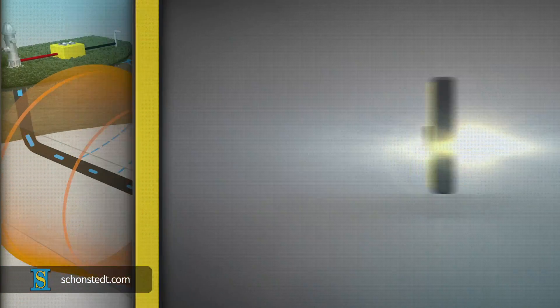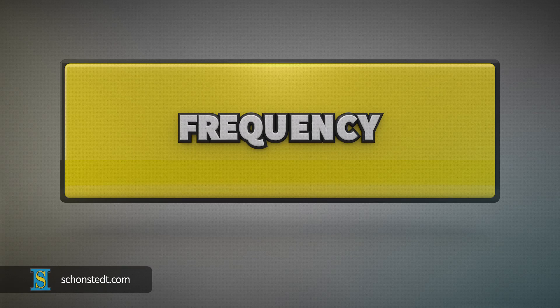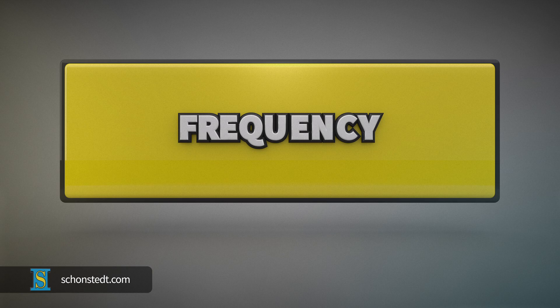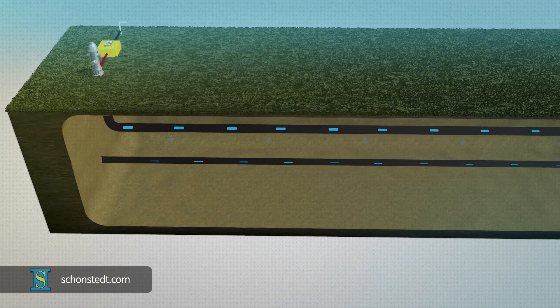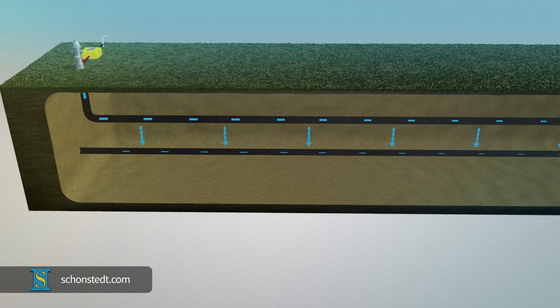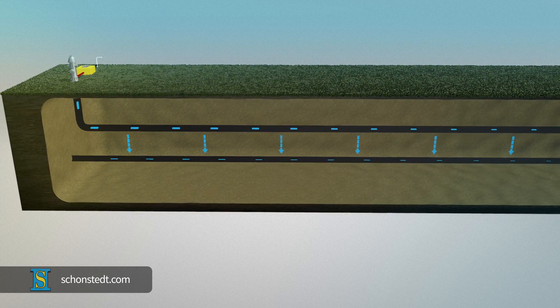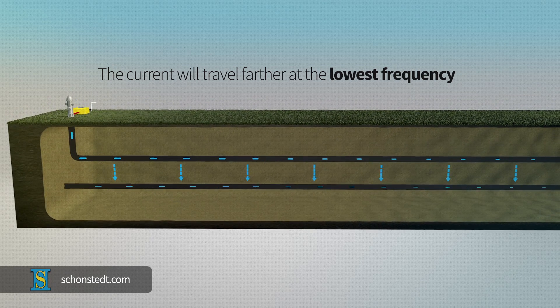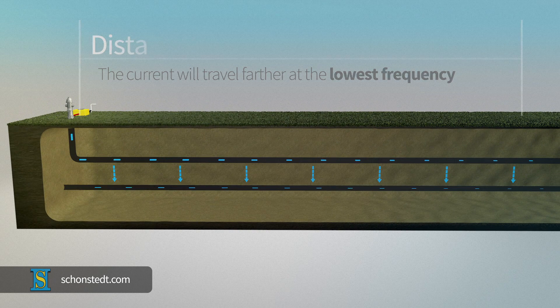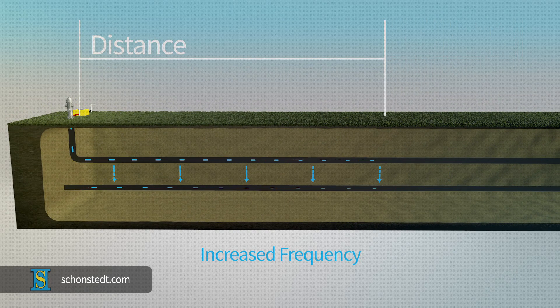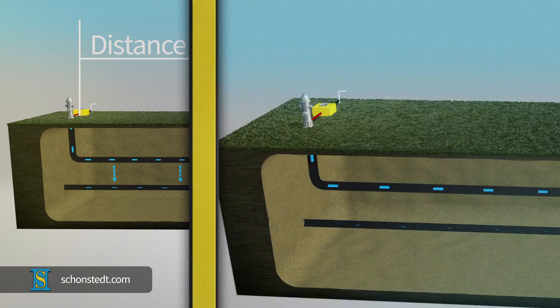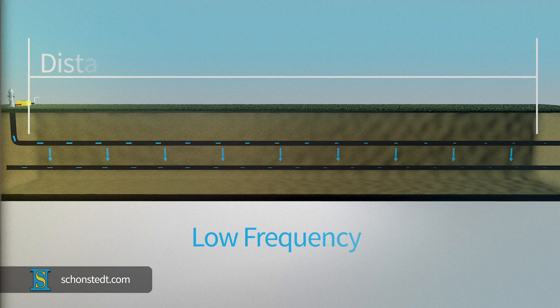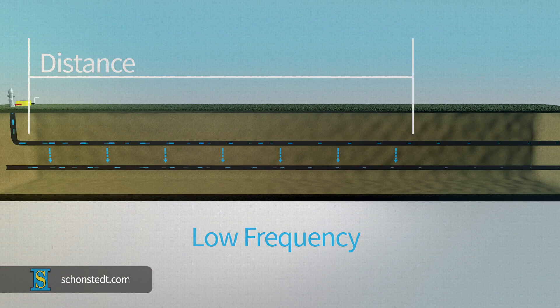One of the keys to getting a good signal is applying the proper frequency. If conditions are good—good conductor, connections, and soil conditions—the current will travel farther at the lowest frequency with less leakage to adjacent structures. An increase in frequency will cause the signal to leak sooner and cover less distance. As a rule, always start with the lowest frequency possible and increase as needed.